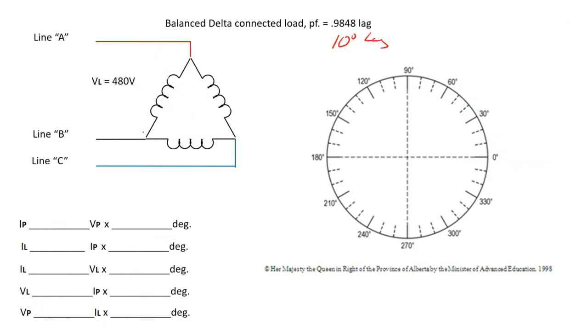And that's a lag. So once again, you have your 480 V phase, so VAB is 480. And whatever current is allowed to go through there due to its impedance is also going to be delayed, 10 degrees lagging that voltage. So putting our one and only voltage on, VAB, we got to draw that current back 10 degrees, right? Let me try that again. That's better. That's 10 degrees, pretty small there. That's I phase, which is your IAB.